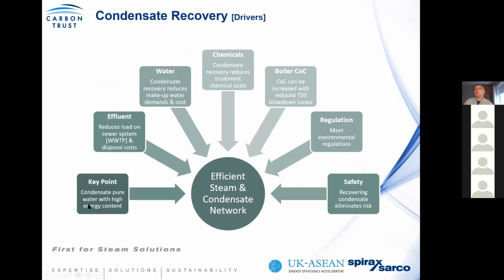So when we start looking at condensate recovery, we look at the key drivers. Condensate is pure water because it's distilled within the boiler itself. We reduce the cost of effluent. If we have to blow down a lot of water and add makeup water to the system, then we increase the costs of water. Chemicals, boiler concentration, regulation, and safety all have an impact.